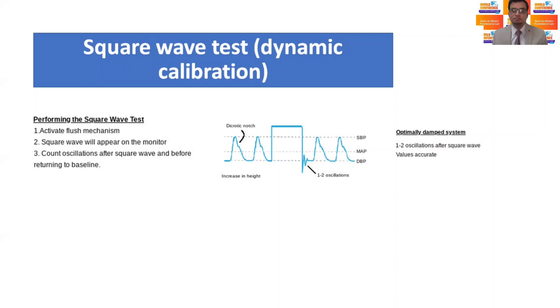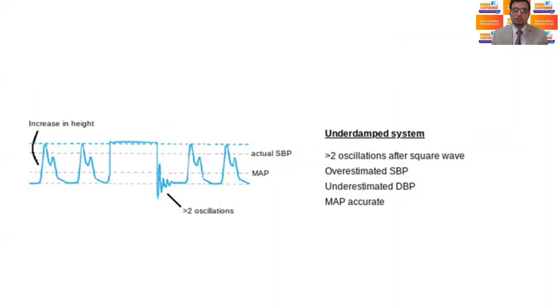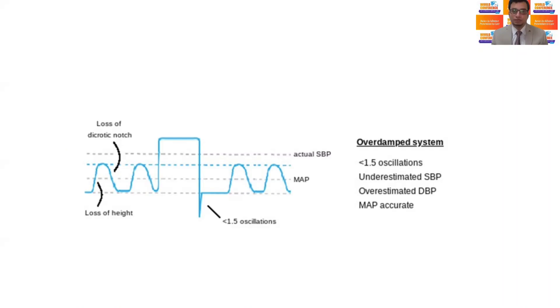If the system is optimally damped, there will be only one or two oscillations before it extends to the tracing of baseline tracing. If the system is under-damped, more than two oscillations will be seen. If the system is over-damped, less than 1.5 oscillations will be seen.